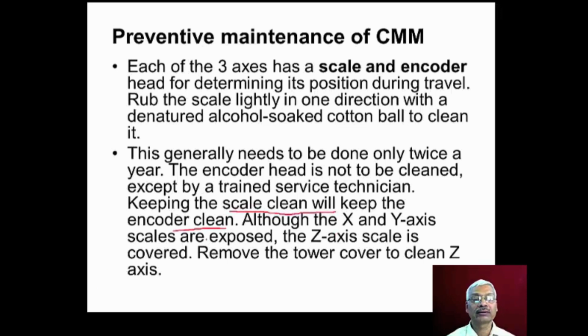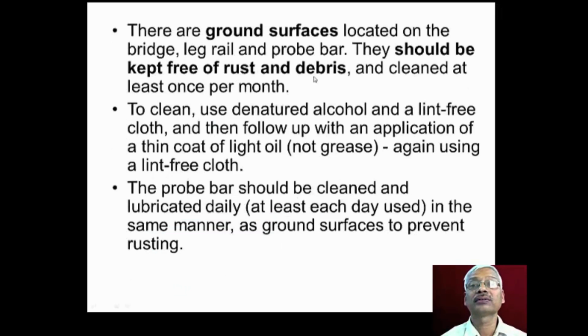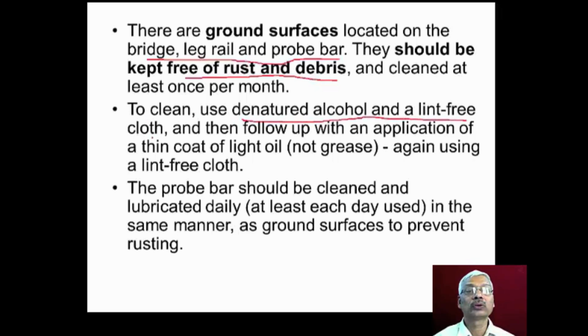Although the X and Y axis scales are exposed, the Z axis scale is covered, so we should remove the tower cover to clean the Z axis. There are ground surfaces located on the bridge, leg rail and probe bar. These should be kept free of rust and debris, and they should be cleaned at least once in a month. To clean these surfaces, we should use denatured alcohol and a lint-free cloth, and then we should follow up with an application of a thin coat of light oil, again using a lint-free cloth.